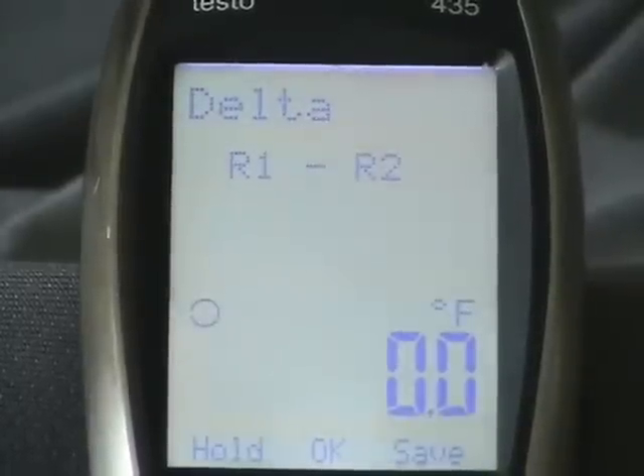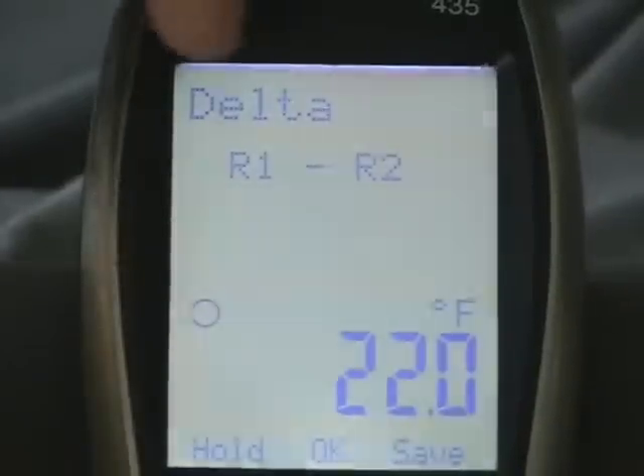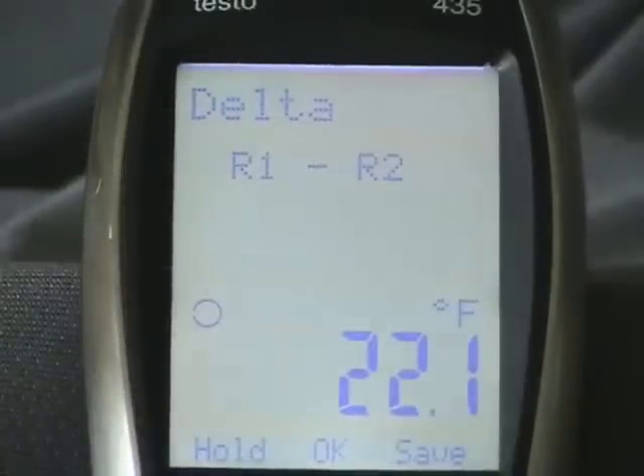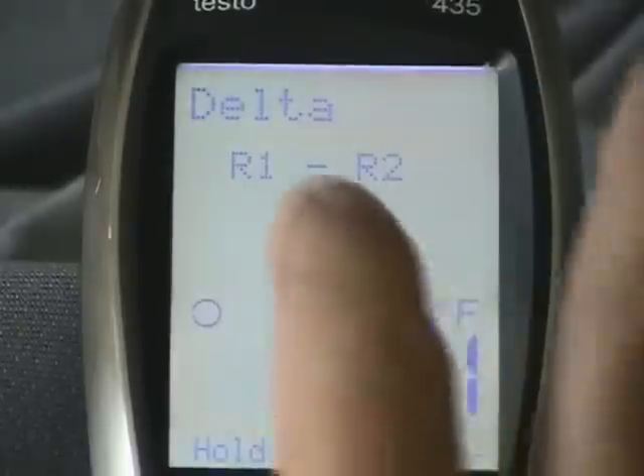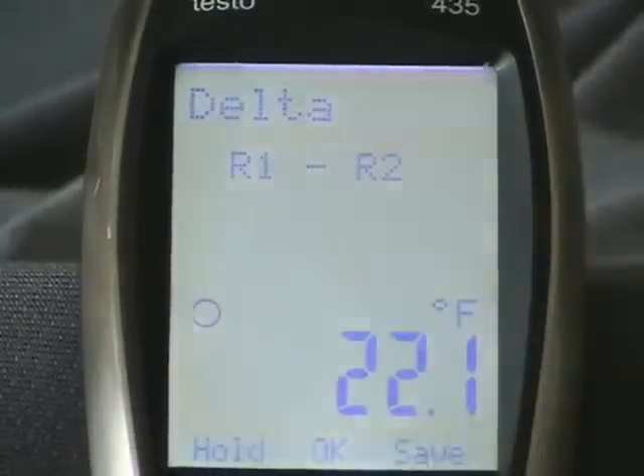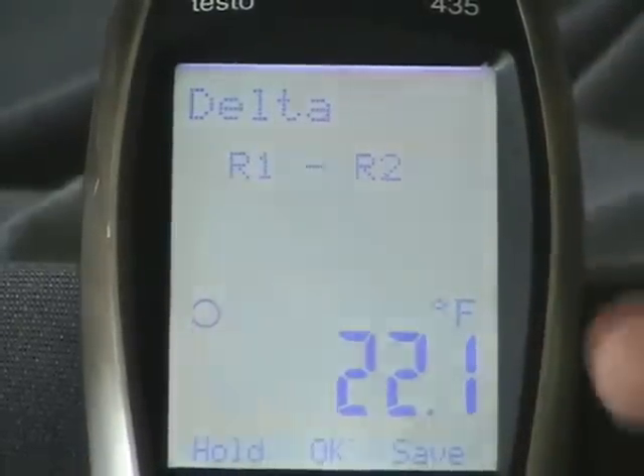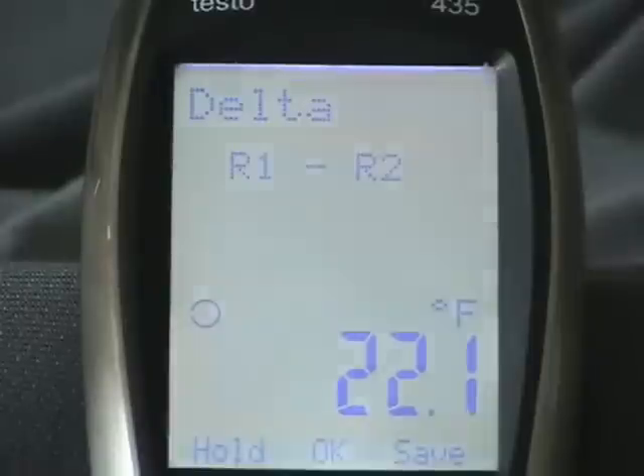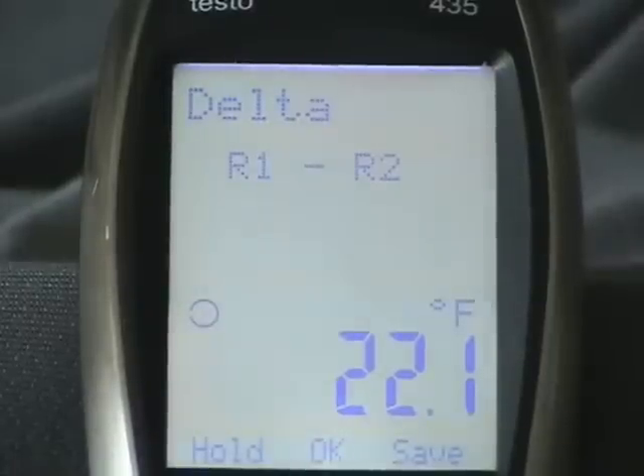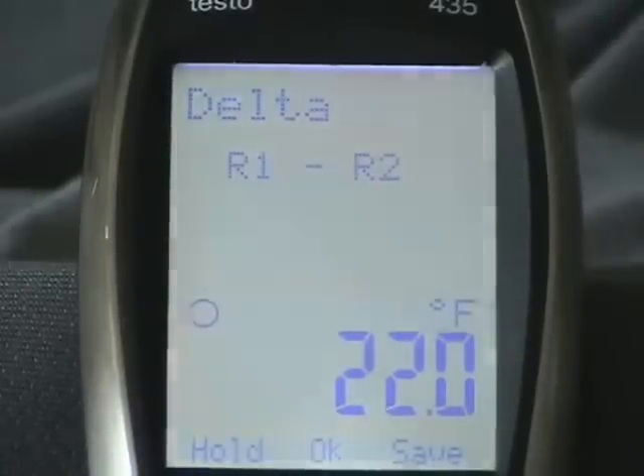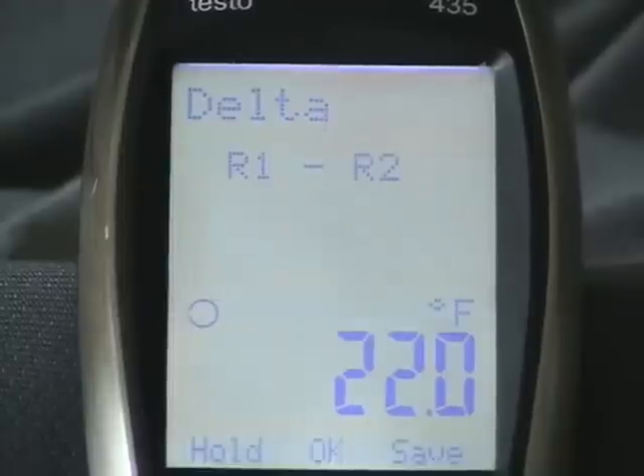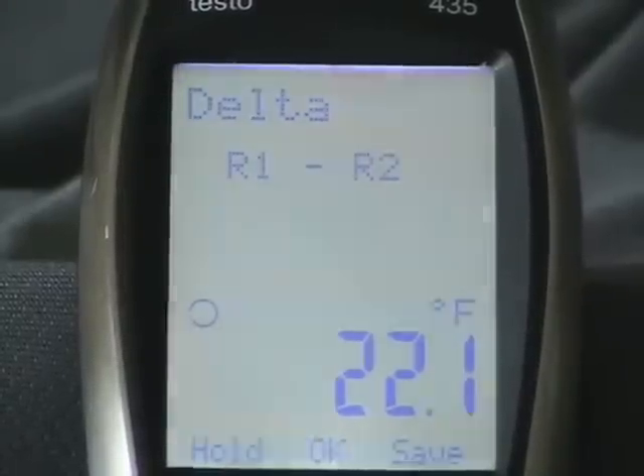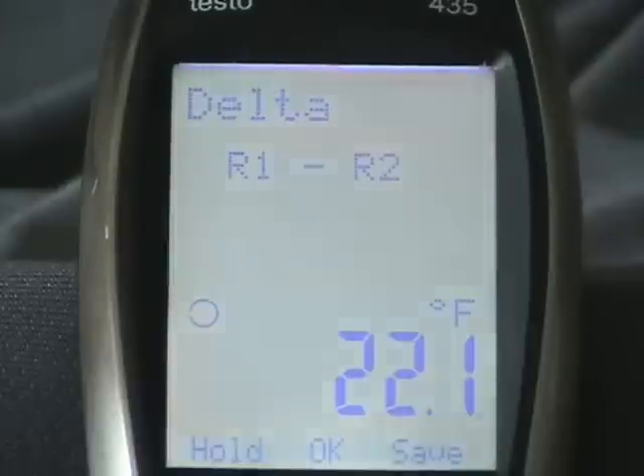So we hit okay, and it shows up here that we're in the delta mode — it's R1 minus R2, and here's the value. You can hold it, you can save it from here. But let's say you're out at the condenser and you're charging a system — if you want to know what the delta T is, you have your probes plugged in, you can look at it here.